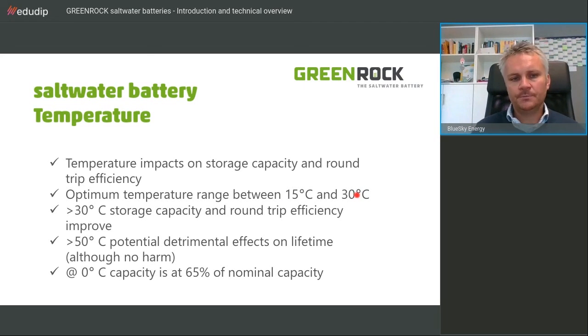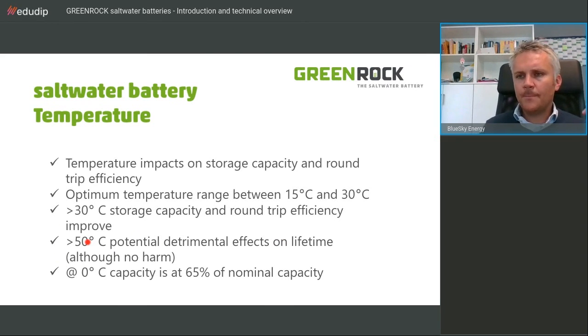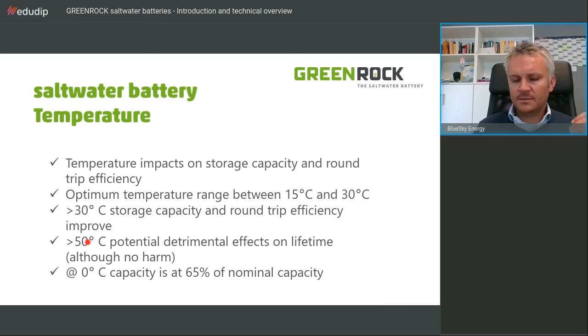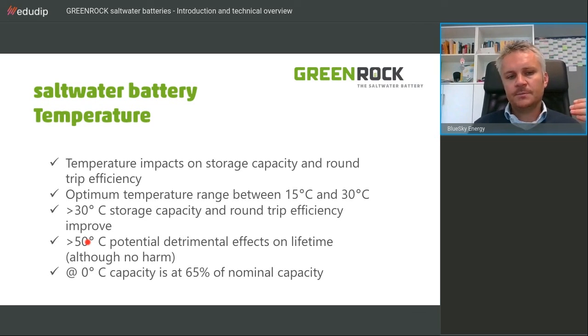And we have got the situation then, and that might sound a little bit funny at first sight, that even if it's getting warmer, our storage capacity increases, and also the round trip efficiency increases. So therefore, the warmer it gets, the better it is. But at temperatures above 50 degrees centigrade, it's still an effective battery.